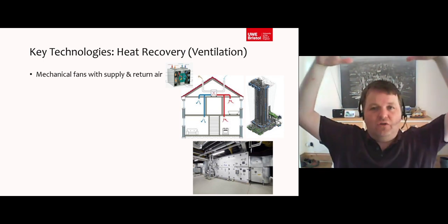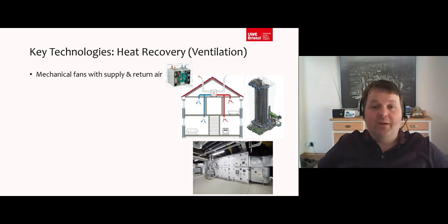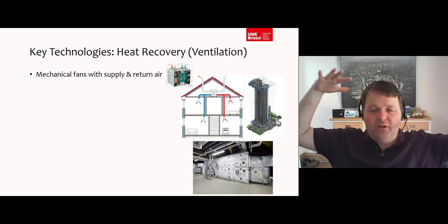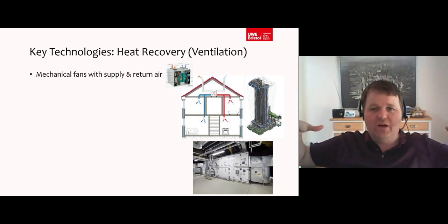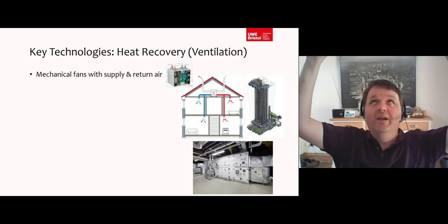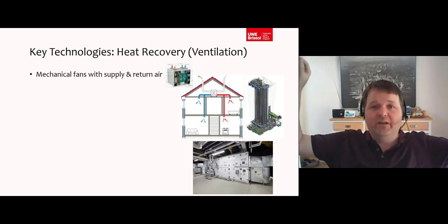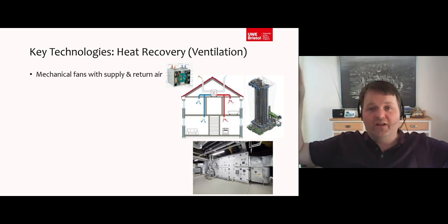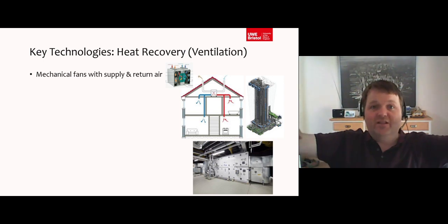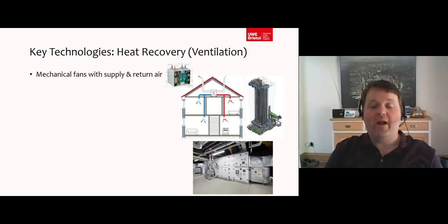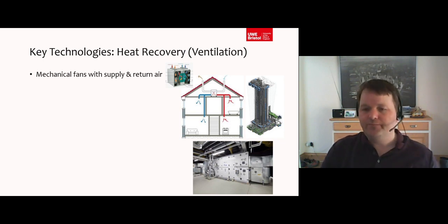It's normally gently introduced to the room at the ceiling level, or sometimes underneath. Gently in multiple spaces so that you don't get any localized drafts. So you notice the shape of the grill is designed to introduce the air comfortably into the space. Sometimes if we want to rapidly increase that air rate, we might use something like a canvas bag system that we can maybe put more air in and disperse it through the space more rapidly if we want to get a higher air change rate through wanting to cool by ventilation rather than artificial cooling.